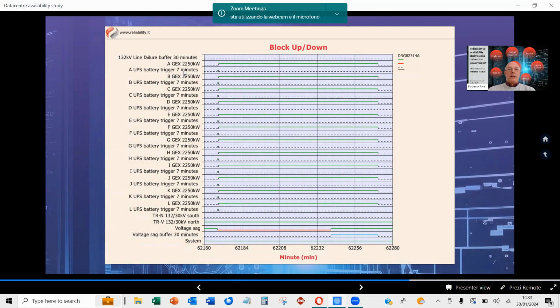And so the battery was represented by a single battery, if you want, lasting a maximum of 7 minutes. But this timing is not actually 7 minutes, it's actually 40 seconds, because after 40 seconds, a generator comes in. And because the failure is upstream, it affects all the system, all generators have to come in. So in this case, you see all the generators coming in.